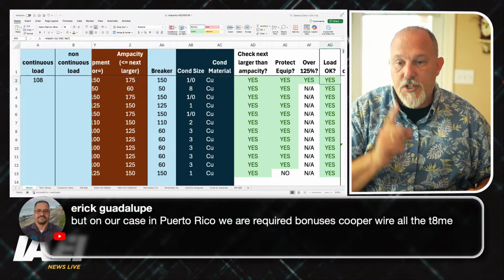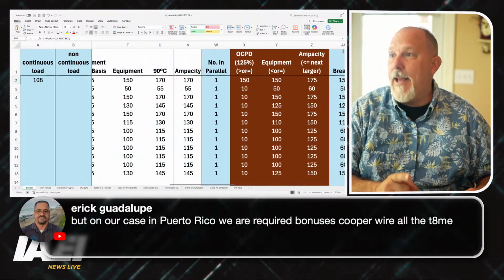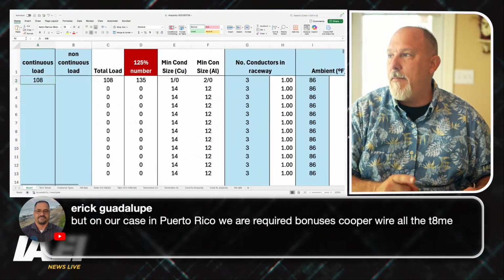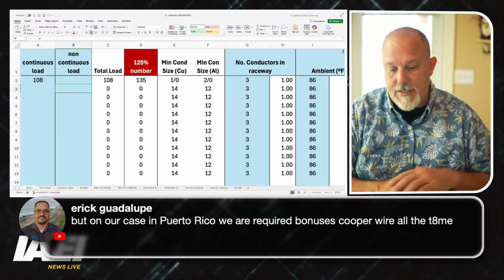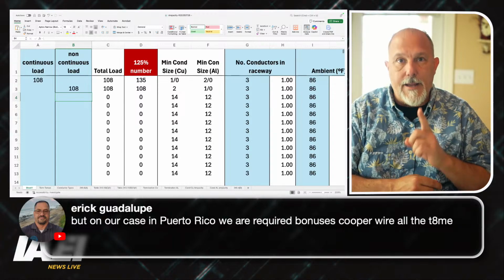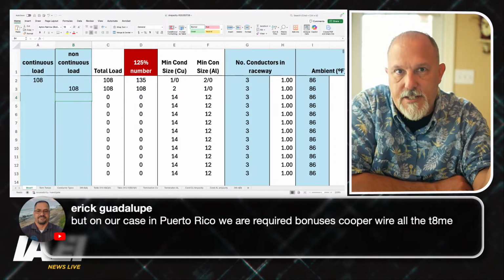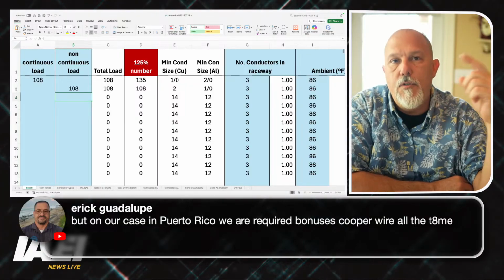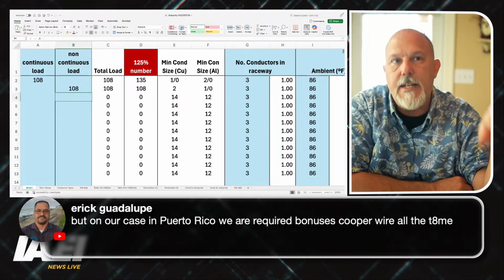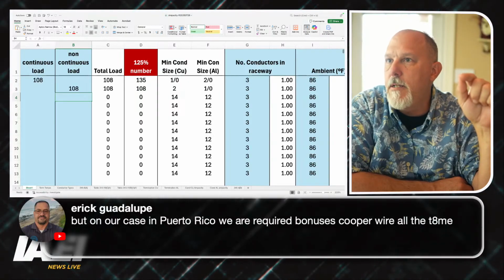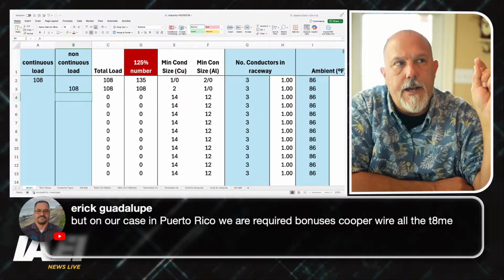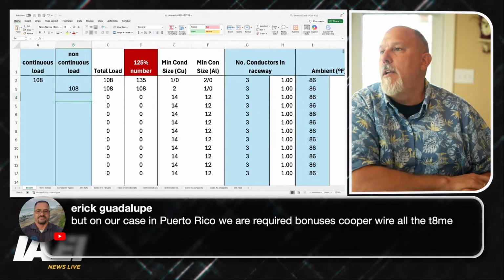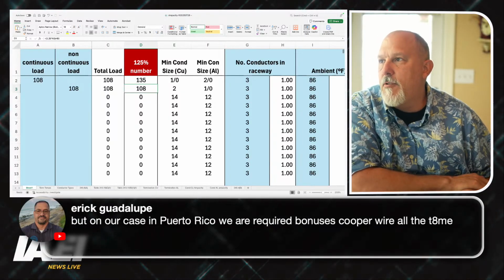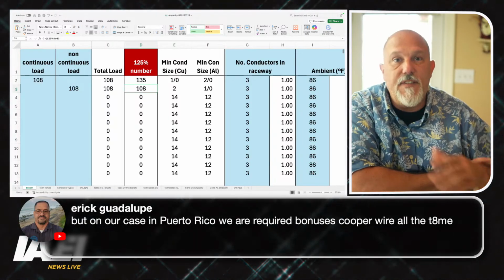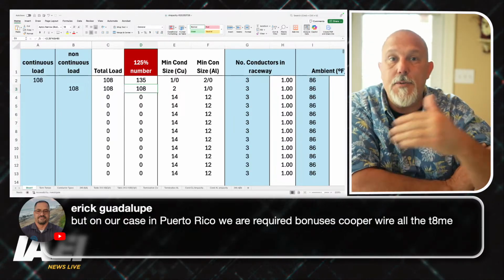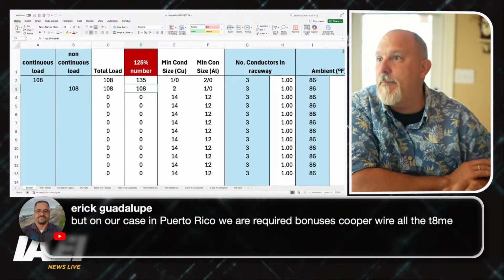All right, so Eric, now I'm going to take this same continuous current and make this a non-continuous load. So I'm going to put it into 108 amps, following the same journey that we just did, going through 210, moving over to 110.14 for terminations, and then 310.16, all that jazz. My total load is 108 amps. My 125% number, the 125% times the continuous plus the non-continuous, is still 108 amps.